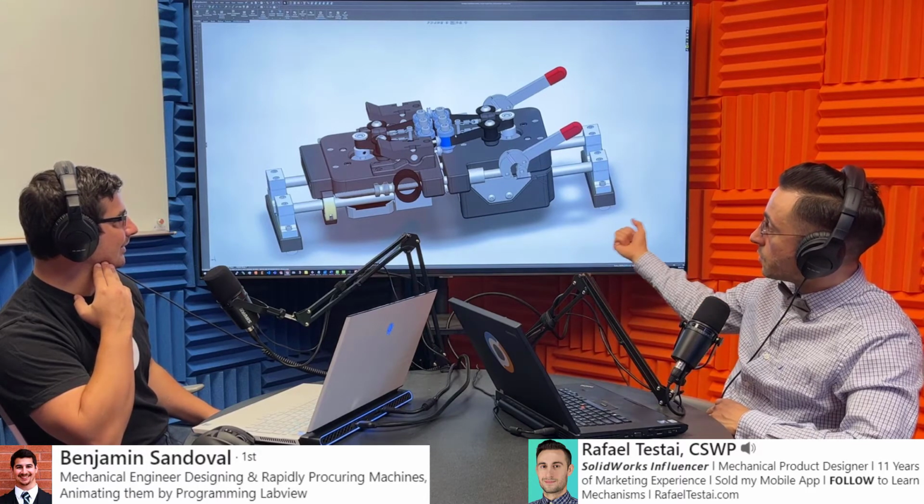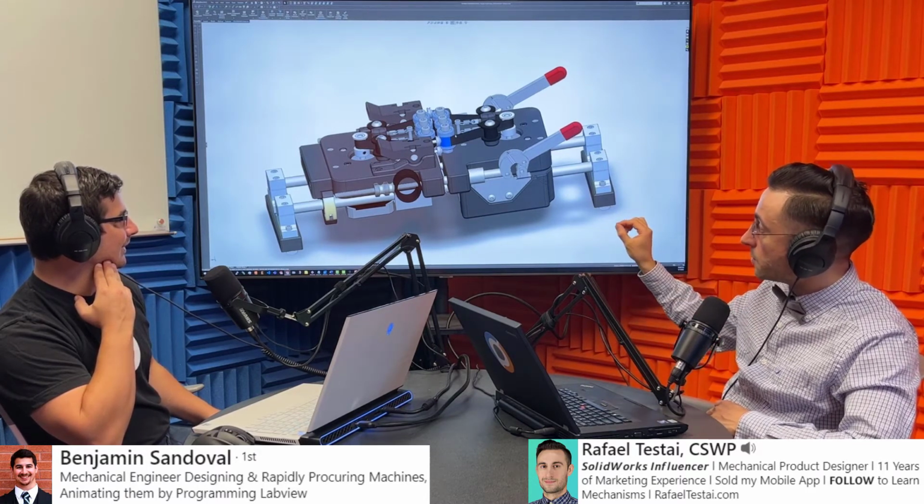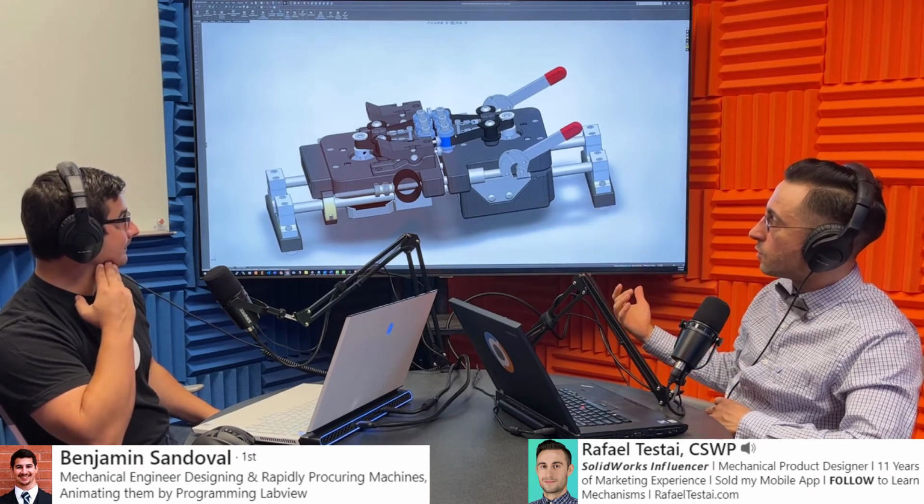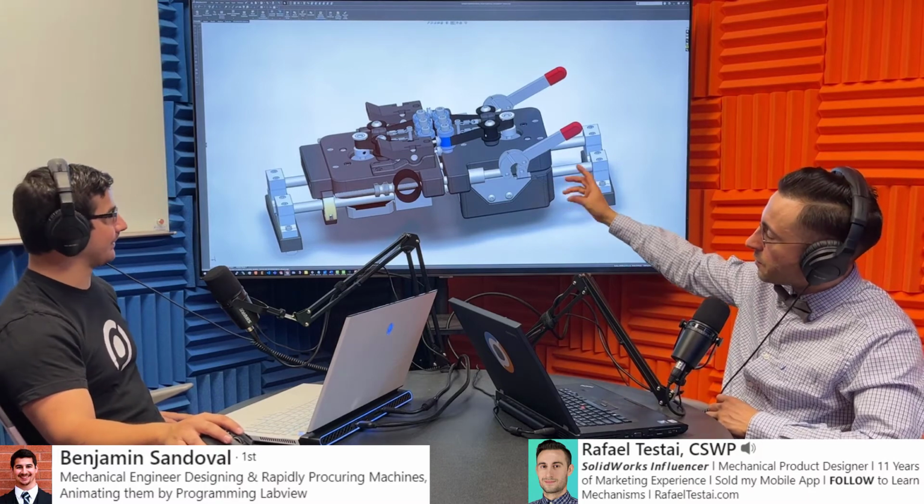I see. So you get it close, you squeeze the cable that's going through. It's like the catheter cable. Yep. And why do you want to squeeze it? Because we're going to drive that catheter into a small tube that has a friction coating or a specific surface, and we're trying to take measurements of the force needed to pass that catheter through those paths.